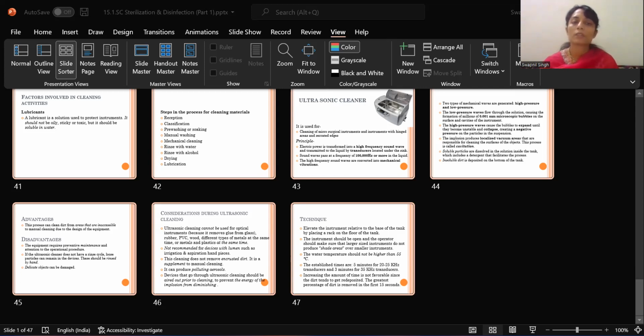Now, the basic action during dry heat sterilization is dehydration and oxidation of microorganisms. It has very little penetration power. Since the heat provided is dry, there is no risk of any kind of corrosive action or rust. It is a very time-consuming process and it can be achieved through two methods, either hot air oven or through glass bead sterilization. Now, the hot air oven. It is an electrically heated chamber and is provided with a fan or a blower to ensure rapid and uniform heating.